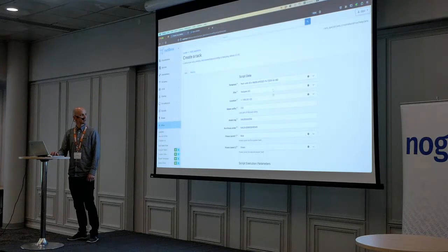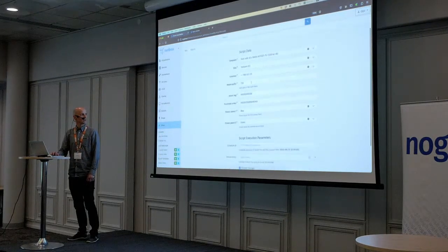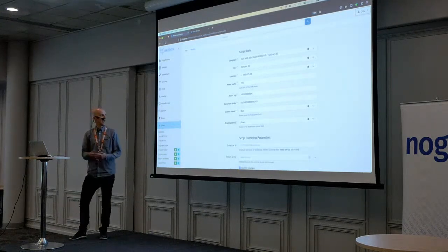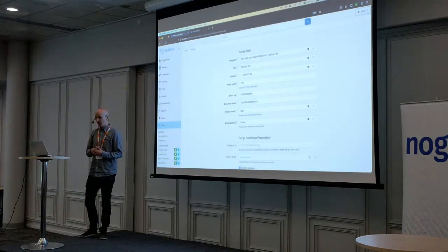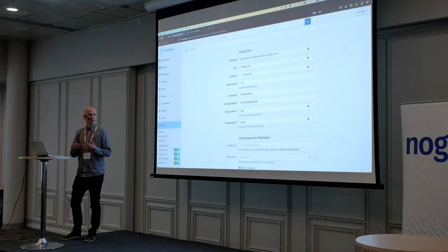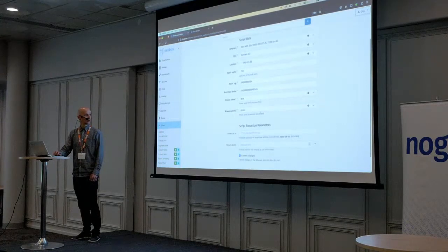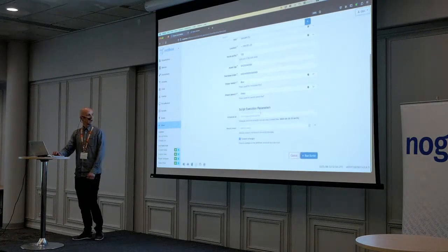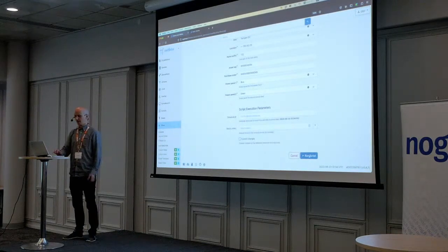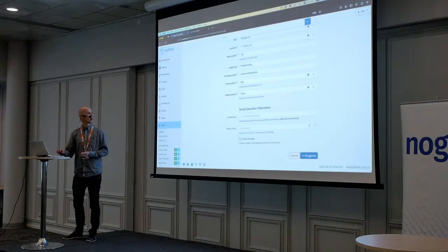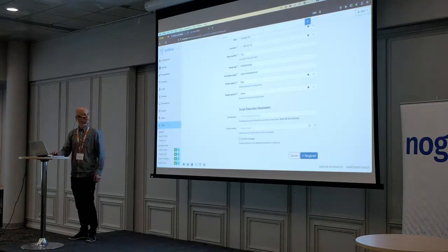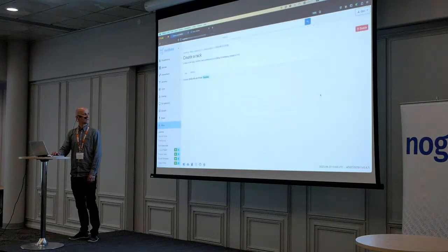We select the site, we select the location within the site, and we keep the name suffix for the rack. We also add some information to the rack, like the asset tag and purchase order, and then we document how the power should be connected. And as I mentioned, this supports transactions, so it's possible to run the scripts as a dry run, so that if, for example, there would be some overlapping names or stuff like that, this would then fail.